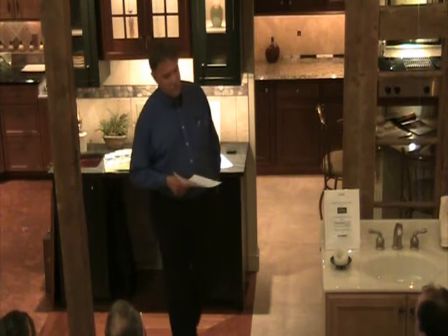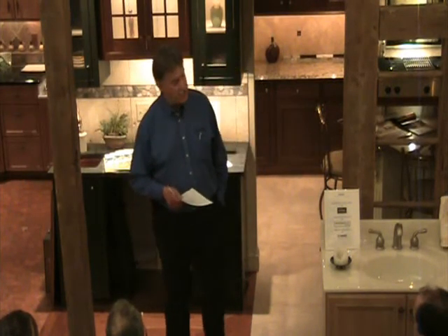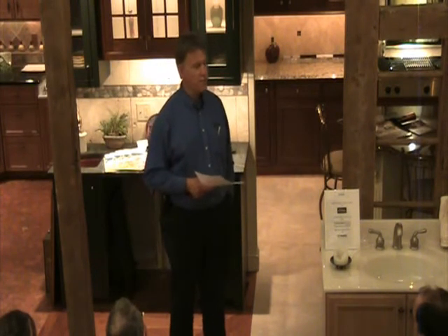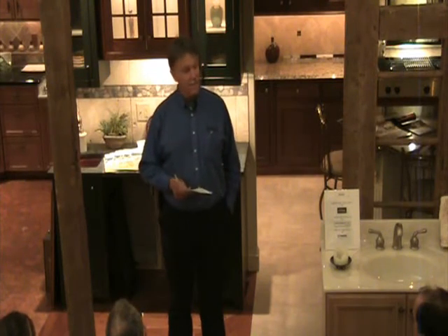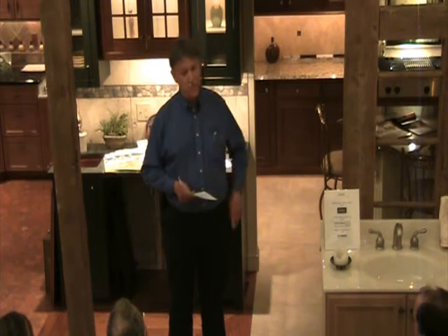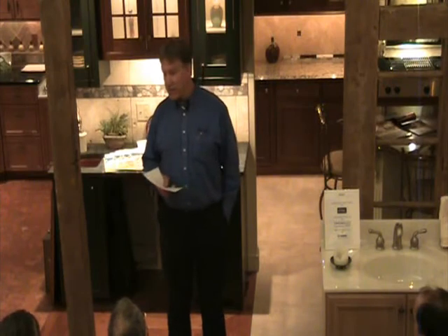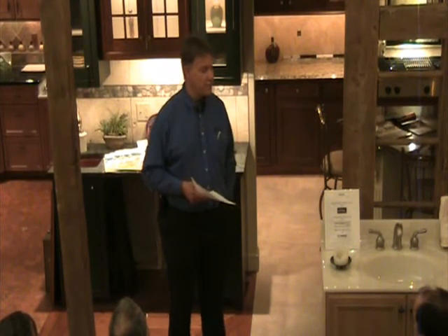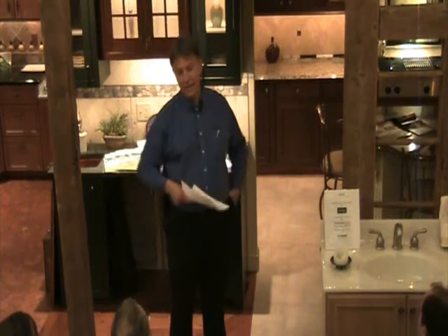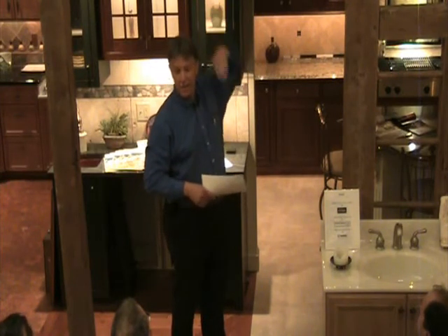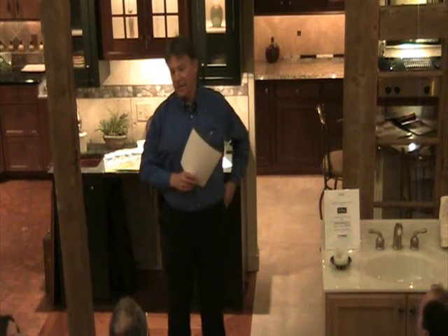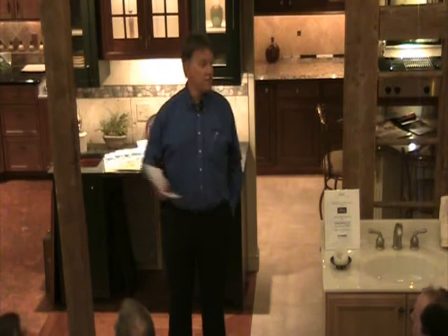Anytime that it's time for a new heating system or an air conditioning system, you certainly want to talk with a professional about it. But one of the things that you want to make sure that they do is to run heat and cooling load calculations. And that's something that's going to take some time to do. You need to figure out the square footage, the cubic feet of space that you're heating or cooling, because certainly, as you can imagine, a room like this, if the ceilings were all this high, is a whole lot different than the 20-some foot ceilings that we have in here. And the amount of glass and the direction that it's facing.